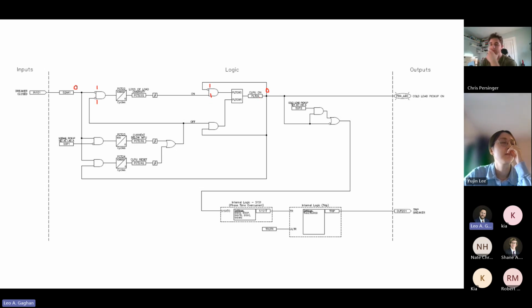And that is what is going to turn on our cold load pickup. So after 15 minutes, our cold load pickup is going to turn on. We no longer have a 0 there. We now have a 1. So now we have a 1 right here. We're going to have that LED illuminate, letting everyone know that the cold load pickup is active.